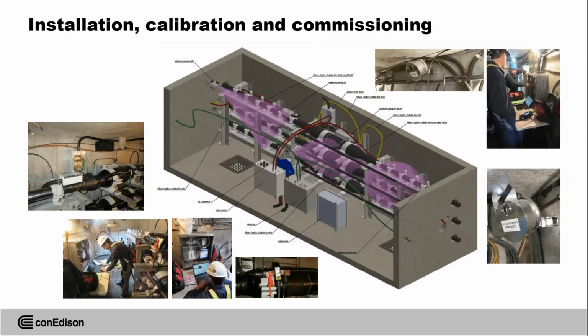The middle camera normally we turn on as an infrared camera, but it can be turned remotely to regular camera and also do this regular visual inspection. And you can see here on the left side, where my cursor is right now, this is local vibration monitoring sensors. In addition to fiber, we also install local vibration sensors just to validate what we have in the manhole, in the vault, sorry. Then you see here technician basically performing the calibration of the system, same thing on the bottom. On the right side, you see cameras with a submersible enclosure installed there.